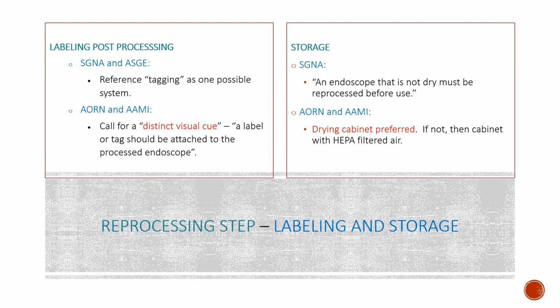When it comes to storage for flexible endoscopes, the important preface from everyone is that scopes need to be dry first. Moving forward, endoscope storage cabinets with only passive airflow should not be used. AORN and AAMI state that drying cabinets are preferred, but if not available, then cabinets with active ventilation are required. To handle an endoscope post-processing to or from the storage cabinet, hand hygiene, clean hands, and clean gloves are required.